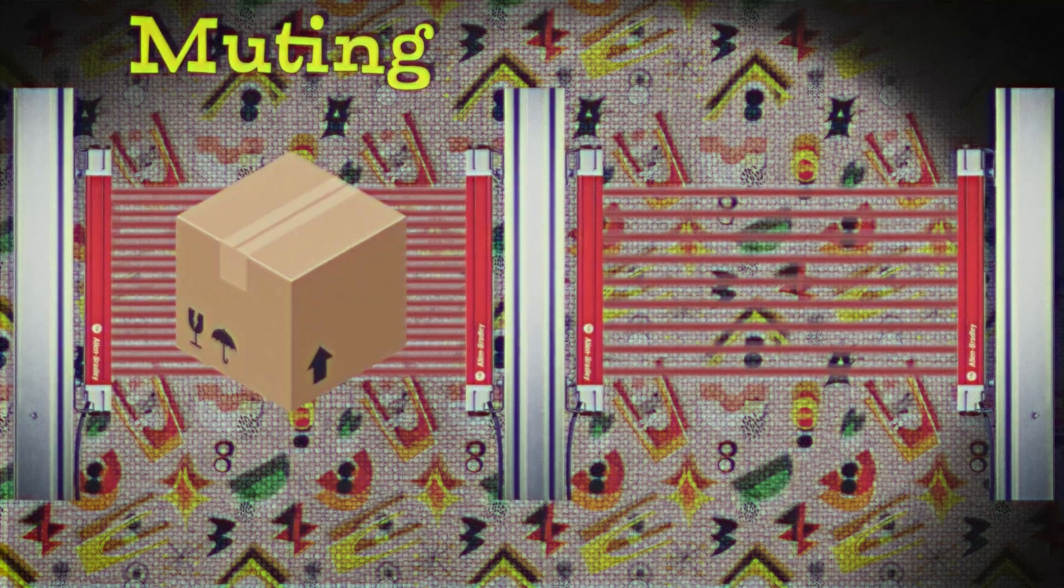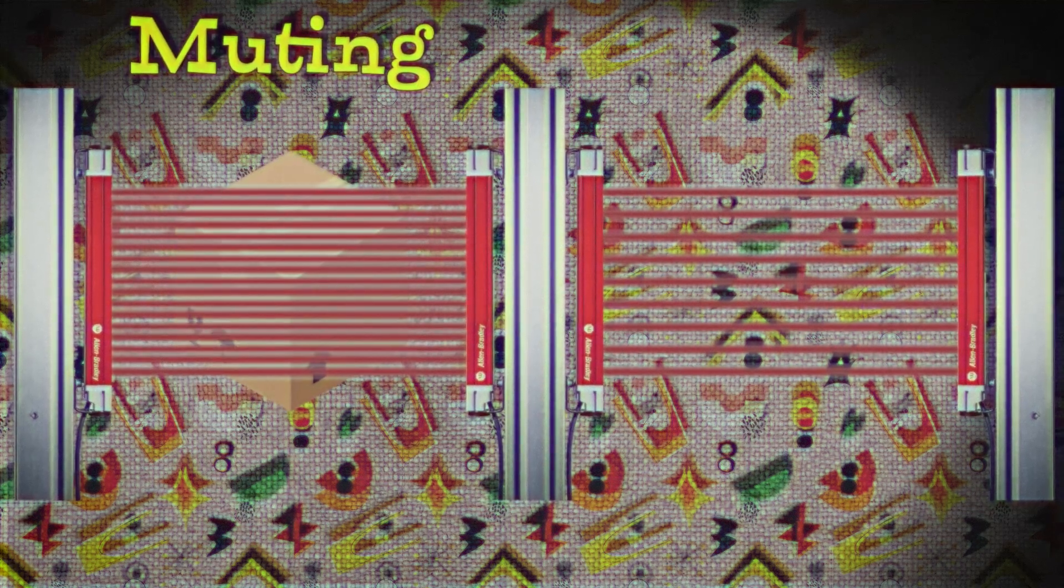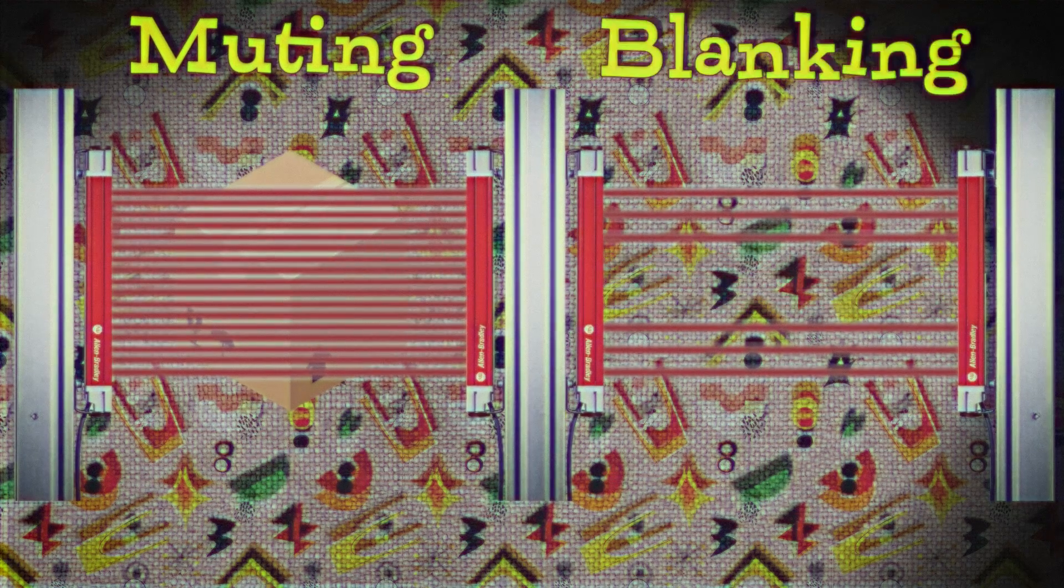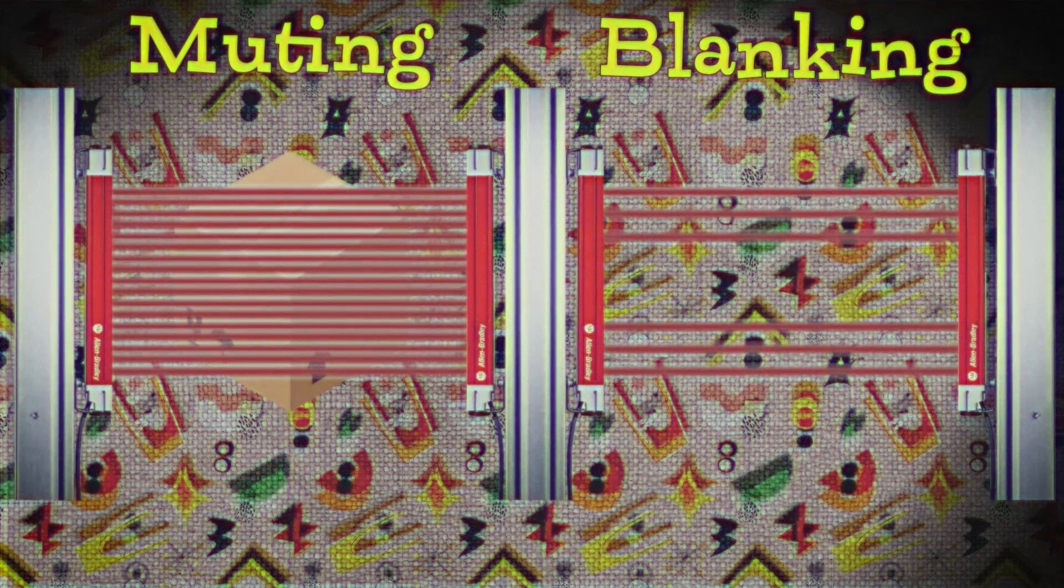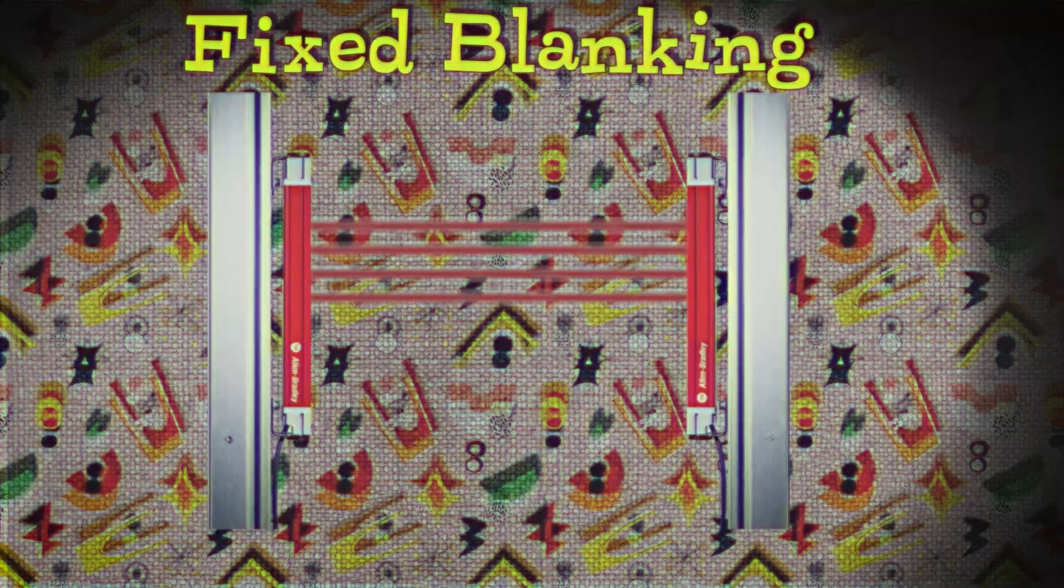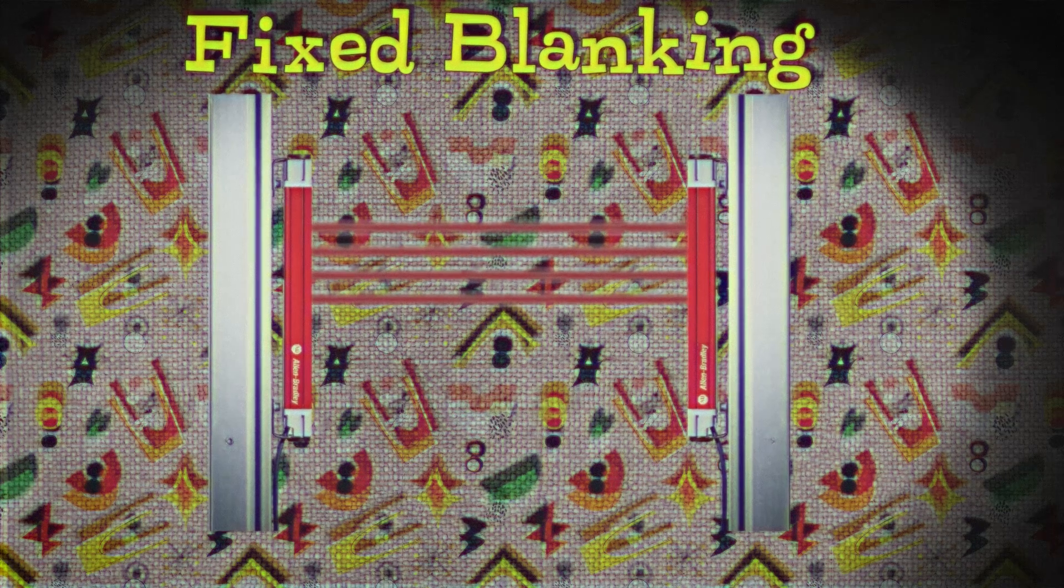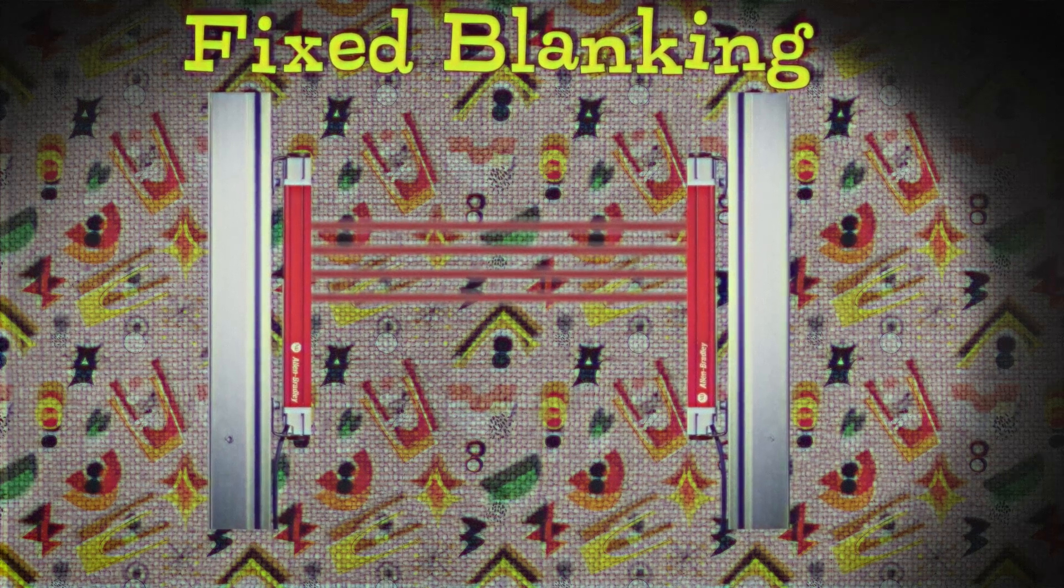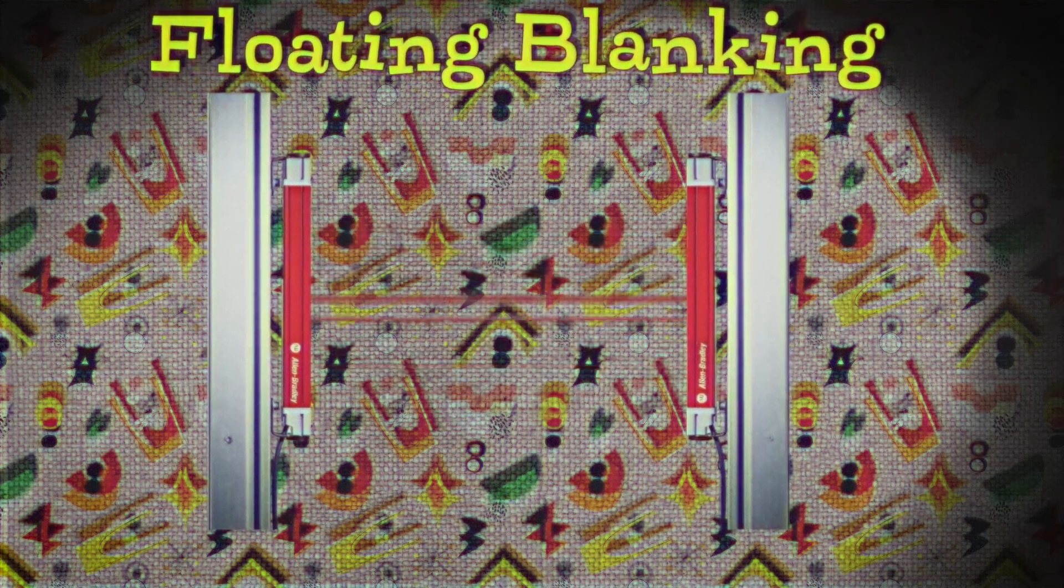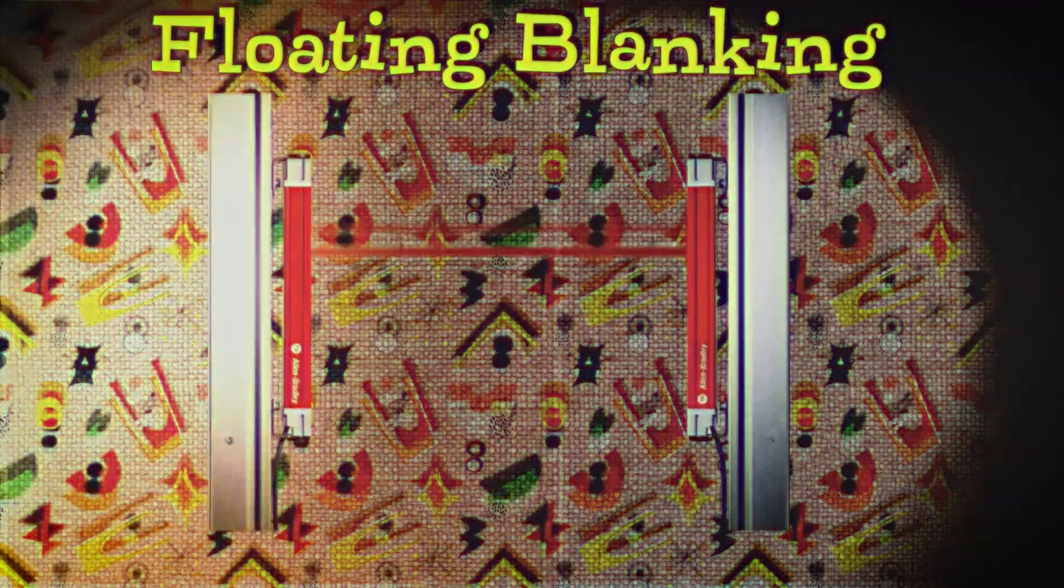With the 450LE we get the ability to do muting. Basically I can tell it to ignore an object that's passing through the field at certain times. Or I can do blanking. I can blank out a portion of the light curtain. A couple of these beams. Fixed blanking which you block just a portion of the light curtain itself. Or you can have floating blanking where you can have one beam that moves up and down.